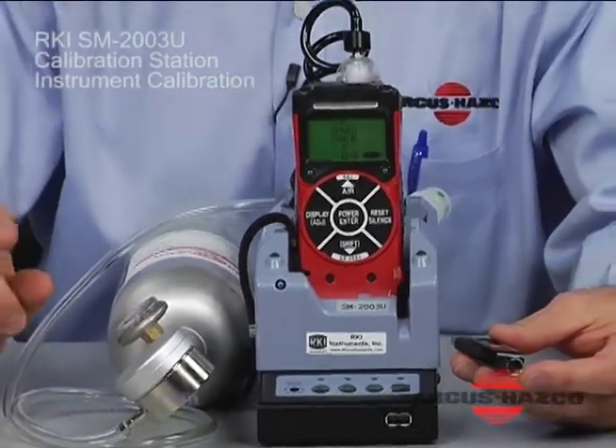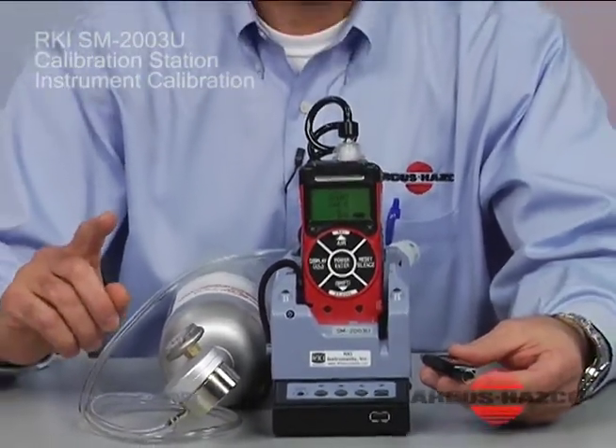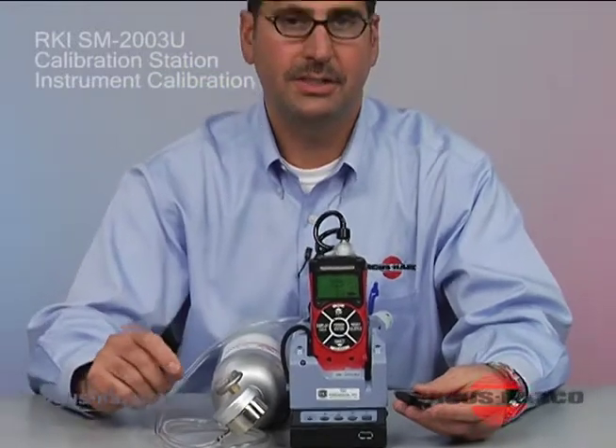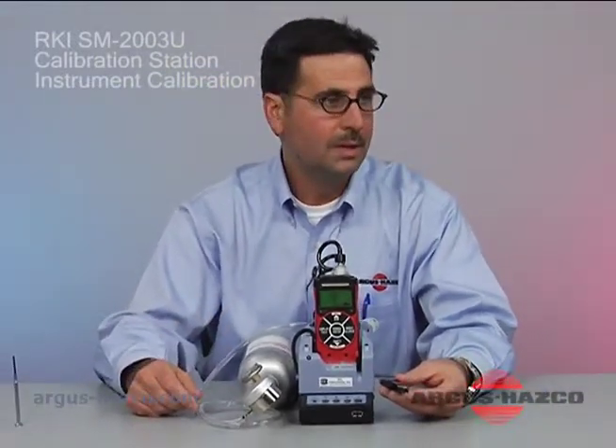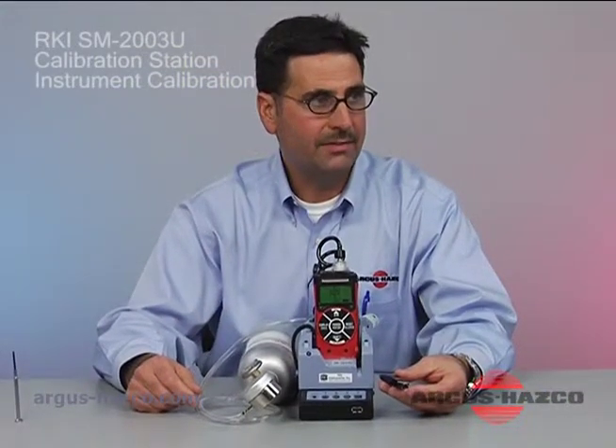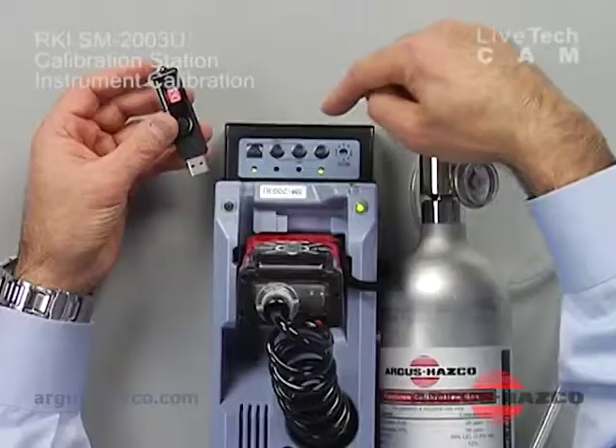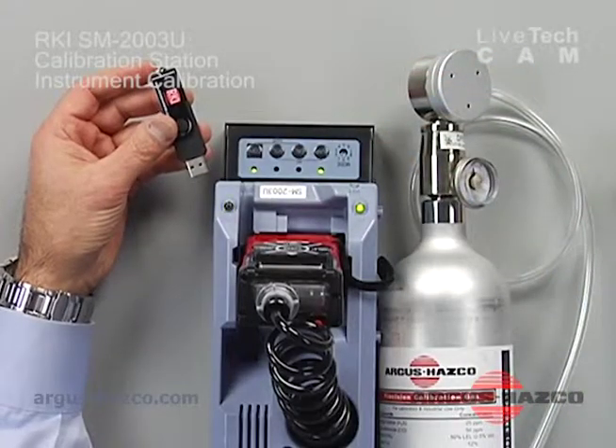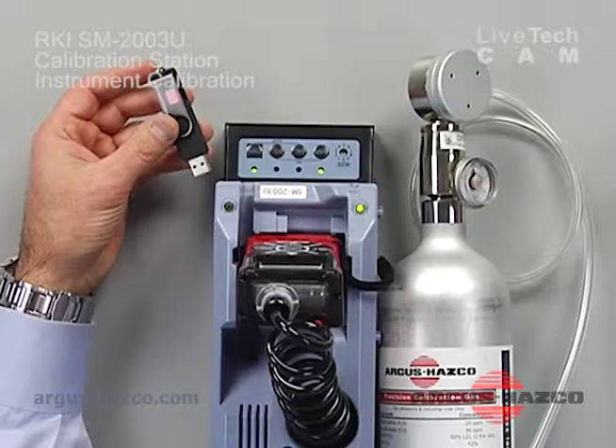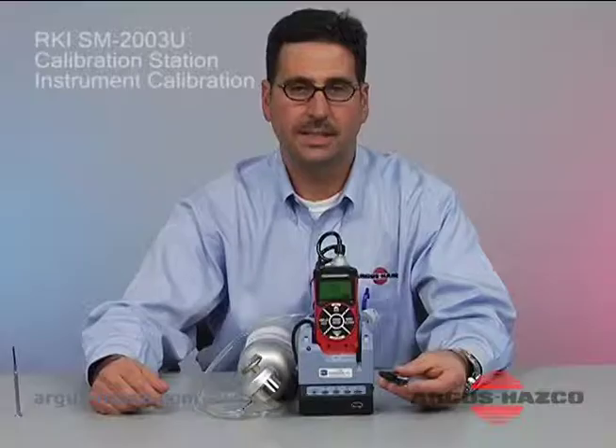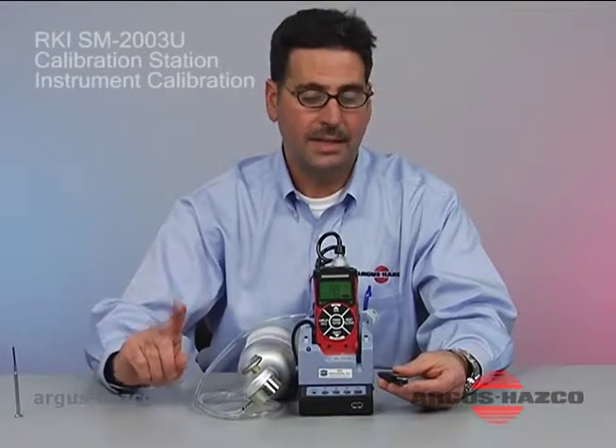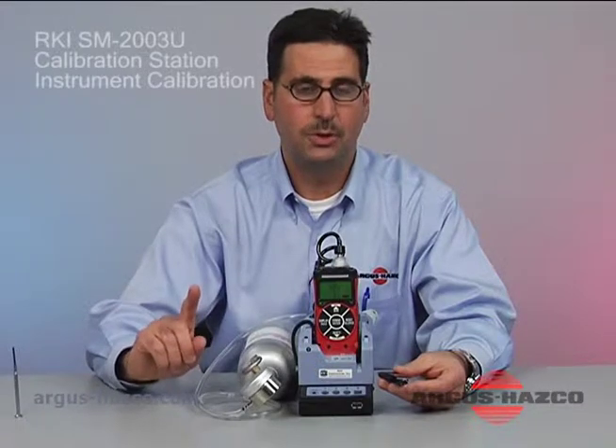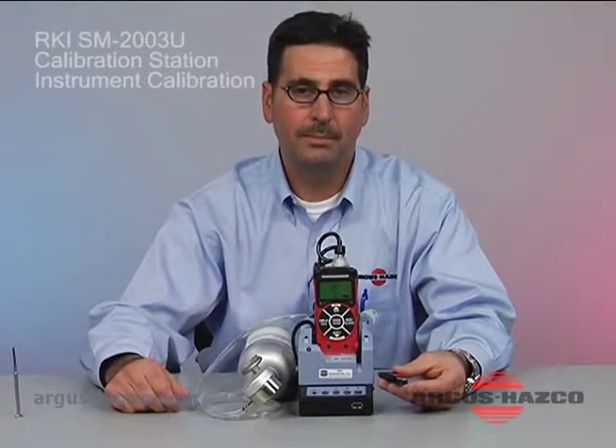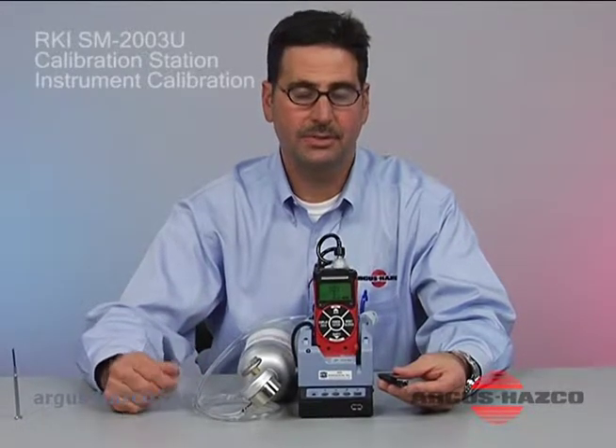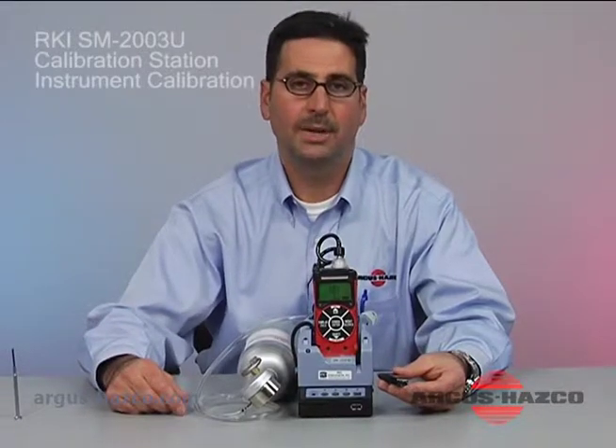The cal station information is not lost. It remains in the cal station until it's up to you to push the button that's identified. Actually, you have to push a series of buttons. It'll indicate to you which buttons to push to erase the information that's on the cal station. Again, the cal station itself is able to retain 200 inputs, whether they're bump successes or failures or calibration information.